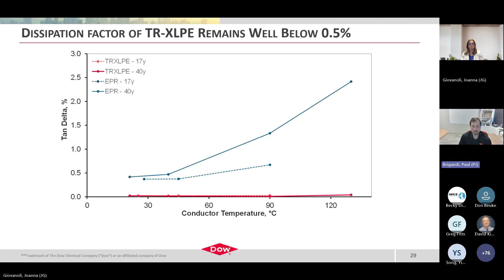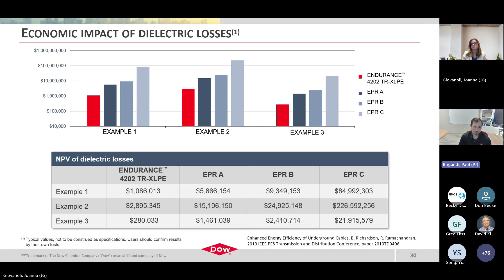This also means we can have a real economic impact. There was some work done about 15 or 16 years ago, a paper that modeled various cable designs with various materials. If you look at the impact of dielectric losses alone across the different types of materials, you see a very significant difference in the total life cycle cost across the life of the cables, depending on the material you choose. So depending on how you're looking at a data center build, how you want to design it, and as you look ahead for more efficient transfer, these types of materials are very suitable and can provide significant benefit for a sustainable future.